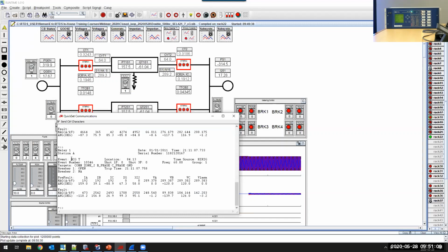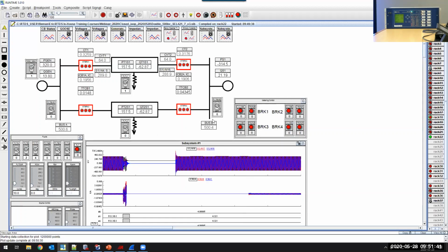So the event is the BCGT, BC phase to ground, and the location is 84.13. The ideal number should be 82.45. The target is BC phase to ground, and that's a zone 2. Similarly, you have all the values for pre-fault and during the fault. Okay, I think that brings us to the end of the demonstration.